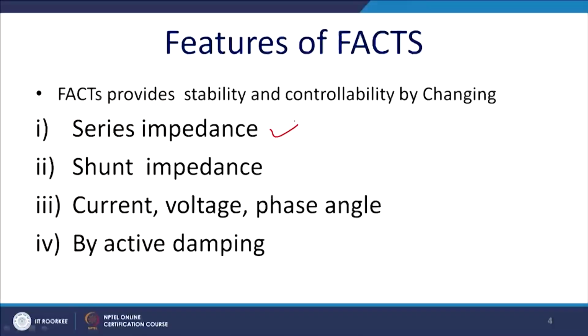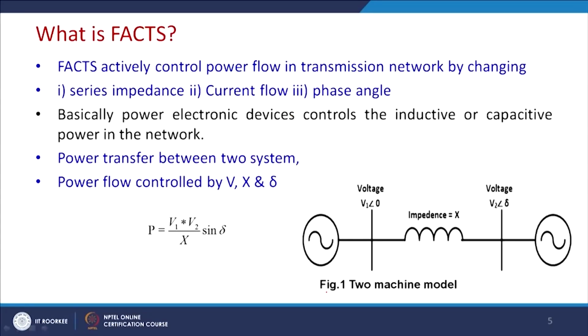Now, FACTS comes with a few features, that is, series impedance. We can change the series impedance of the network by a FACTS controller. Thereafter shunt impedance, current, voltage and phase angle control, and it can also actively damp power oscillations. This is a simple two machine model where energy is transferred from point A to point B with the impedance X. The transmission line is considered lossless, and this is the series impedance X. Power electronics can control this inductive and capacitive power network and thus control X, and thus it can control the power flow between the two lines.